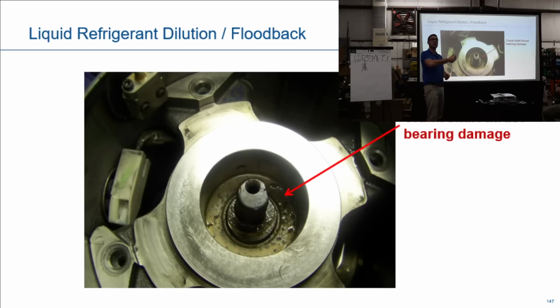Then this is what happens. All that liquid refrigerant comes out there and starts to wash out. What do you think all this stuff is? Metal. And what do you think is just below this thrust surface, right down here? Windings. So now you go up to the compressor and say, oh, it's an open winding electrical failure. But really it was caused by that liquid dilution or flood back.